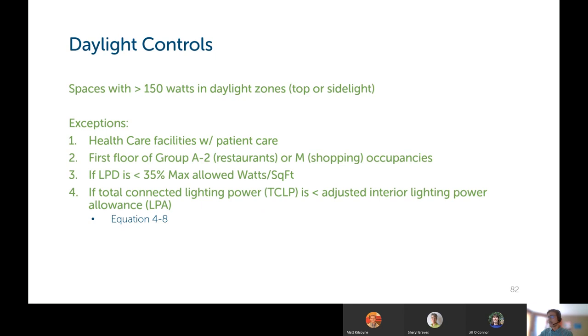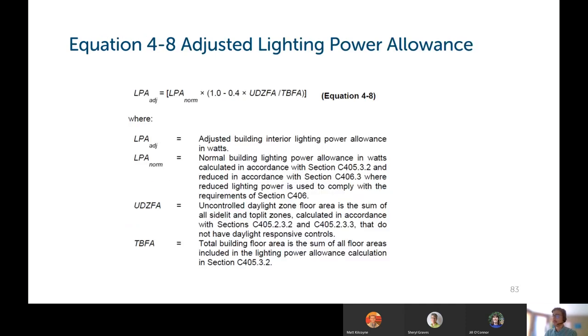And if the total connected lighting power is less than the adjusted interior lighting power allowance, which is equation 4.8 that I will show next. So if the adjusted lighting power allowance equals this formula here, which I won't go into detail on, where you take into account daylight floor areas and the amount of area that's not in the daylight zone, then if you meet this equation, you do not need to do daylighting controls in a space.